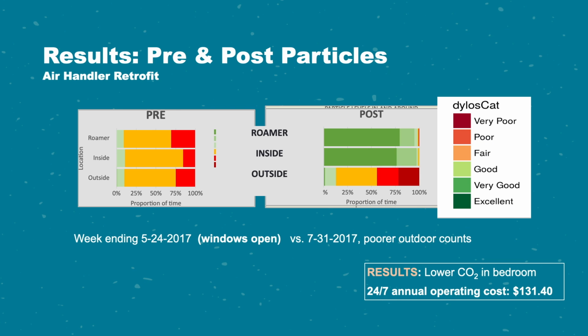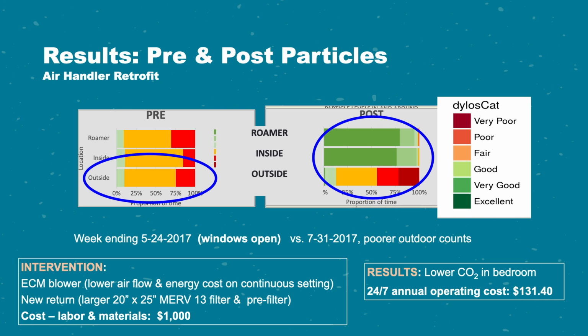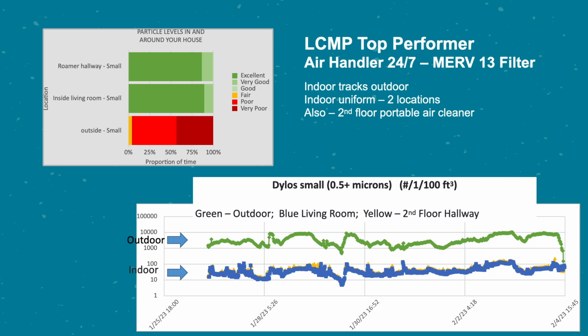Pre-post results typically go from red to yellow to green. The added interesting thing is that because you're running the air handler 24/7, you get better mixing throughout your house. So if you've got a house with a high CO2 in the bedroom, you're going to have better mixing. If you've got a house that's not comfortable in the summer on the second floor, you're going to have better mixing, so even better comfort. So something to consider. We typically do put the larger filter in, not just the same size filter, as well as the deeper. Here you see what's typical, that the air will be uniform throughout the house because of the mixing achieved by the air handler.